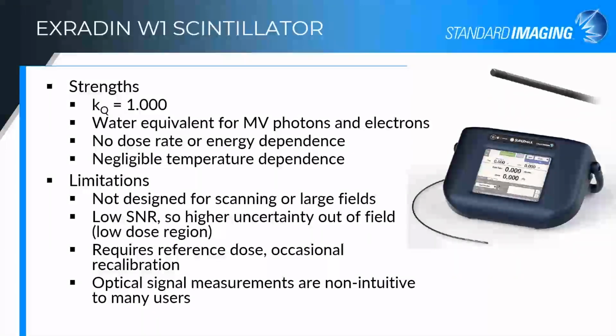So not only are you generating more Cherenkov within your optical fiber, but you're generating it at an angle that is, we're relying on total internal reflection down this optical fiber in order to collect the signal. You are collecting and channeling more of the Cherenkov signal than you are when the detector is perpendicular to the beam. And so the curve, where exactly that curve in the fiber happens, can impact your spectrum just slightly, can impact your uncertainty, and then ultimately impact your measurement. So we do recommend that you use the scintillators perpendicular to the beam and not turn them end on. You can, it just adds some uncertainty to your measurement.